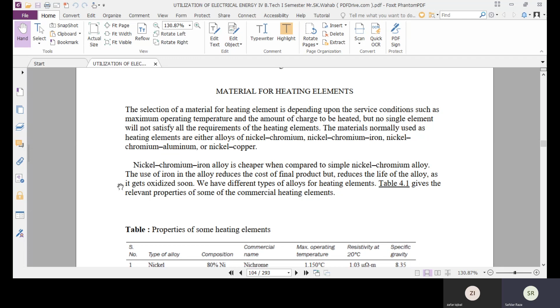We have different types of alloys for heating elements. Table 4.1 shows all of these. From the table we observe the different combinations of the alloys, their composition, their commercial name when we buy it from the market, and the maximum operating temperature range. If our maximum temperature is about 1200, then nickel chromium aluminium is the best. If our temperature is maximum 400 degrees Celsius, then this combination is best. Similarly, if it is 950, then this one, and if it is this one, then nickel chromium combination is the best.